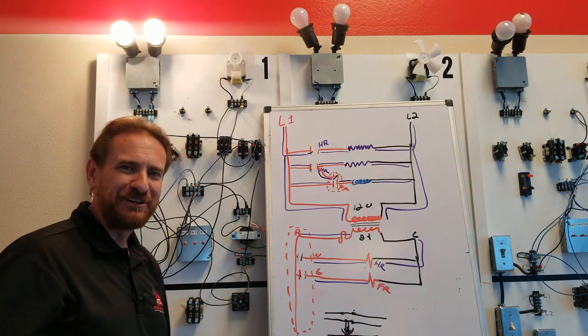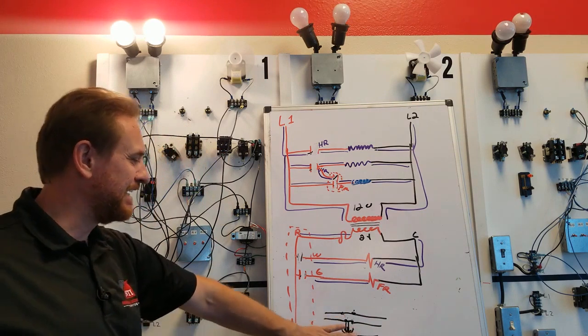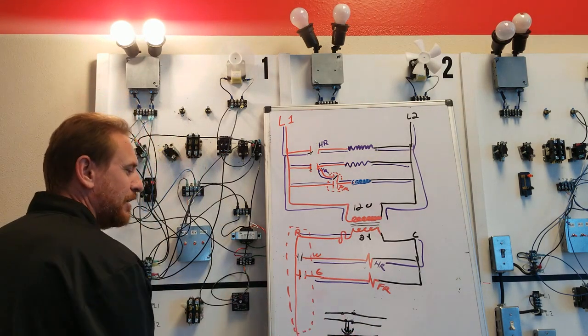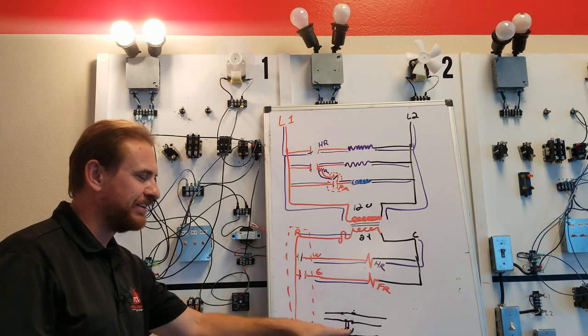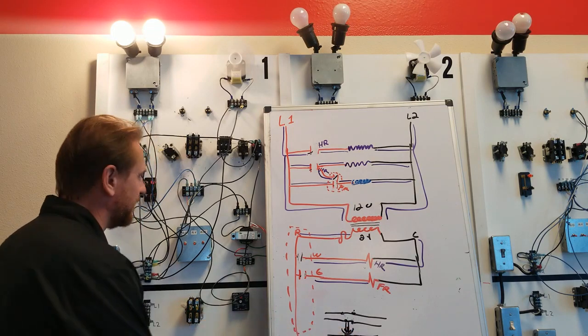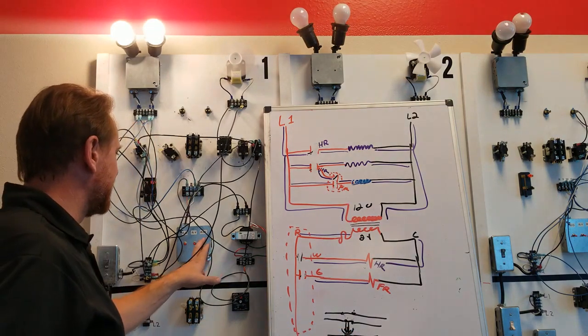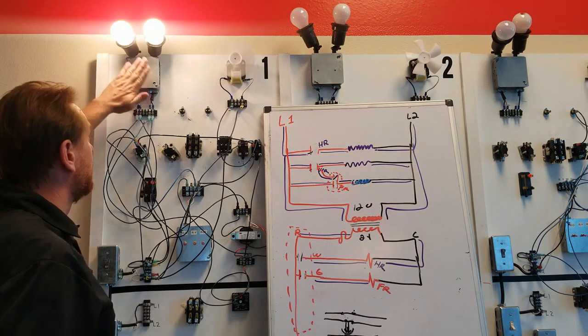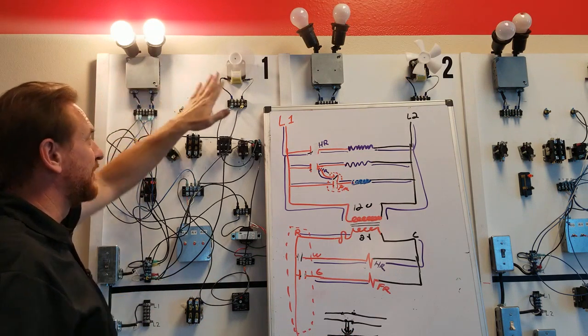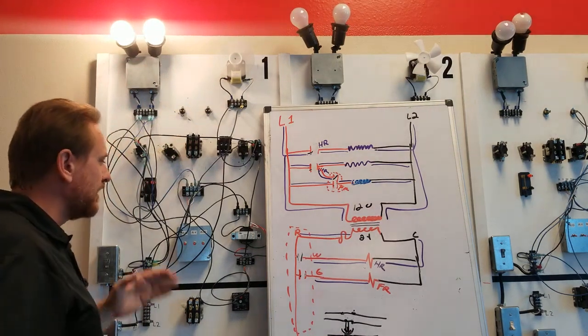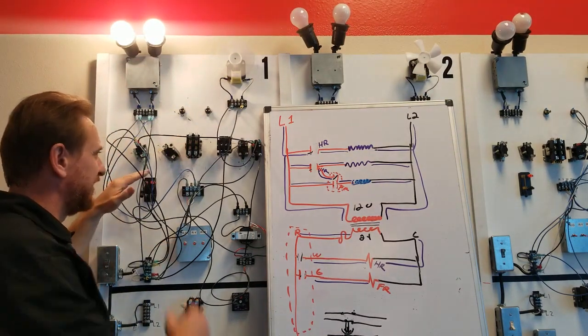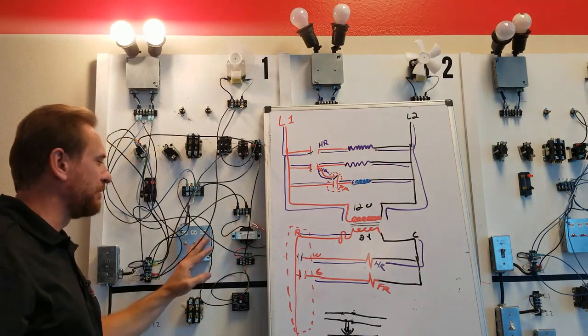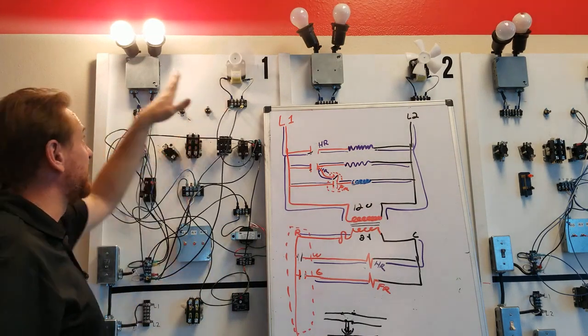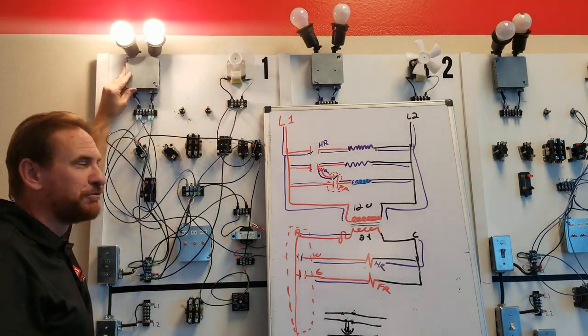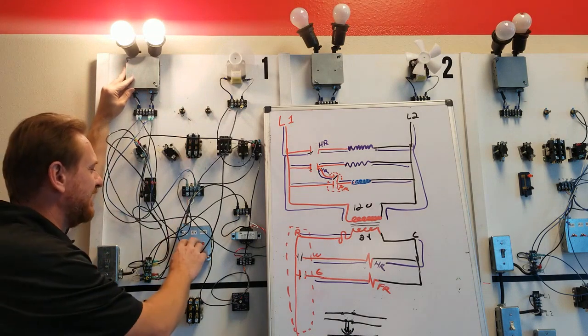It's better if you can do it in person, but what's happening is we're heating this up and it doesn't happen immediately. We can buy these in different types of heaters and different types of bimetal to have a different sequence. So when I de-energize the call for heating, notice that our lights are still on and our fan is still on. The reason this is so important to wire it through this normally closed is if the thermostat was controlling it, the fan would have shut off and our heat elements would have still been on, which would be a bad thing.